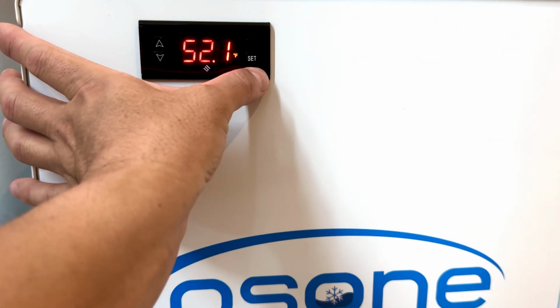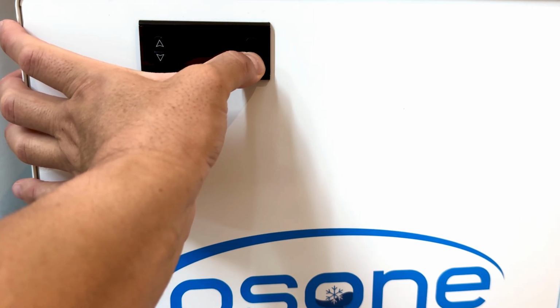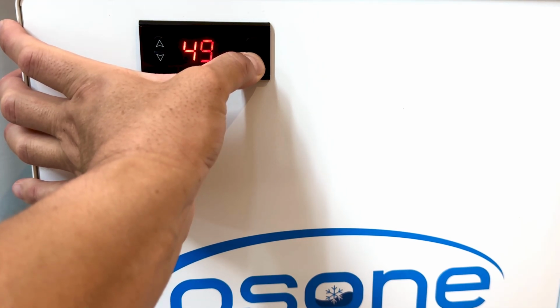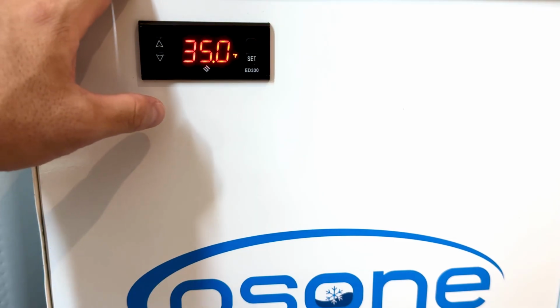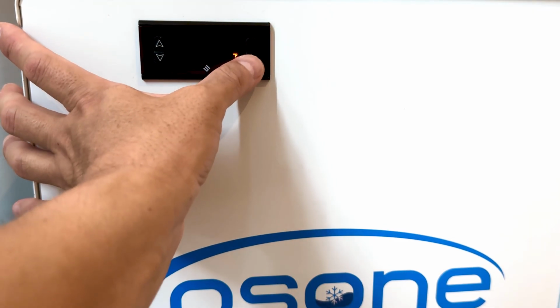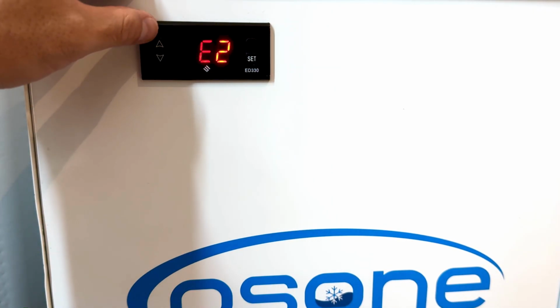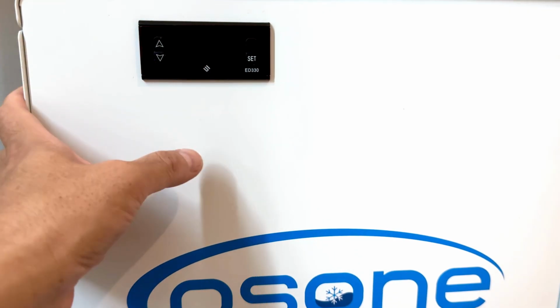Now the advanced settings: you're going to hold the set button down for 5 seconds. You're going to enter into the E1 setting, which is your low temperature alarm. We want that at 35. If you hit set again, you'll enter E2. This is your high temperature alarm. We want that at 100.